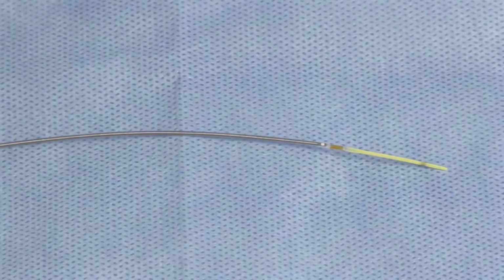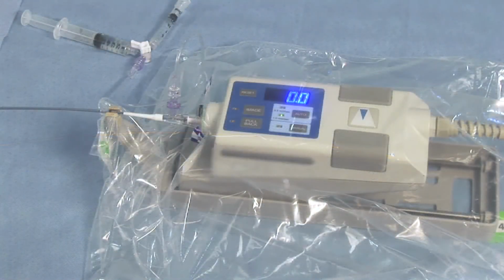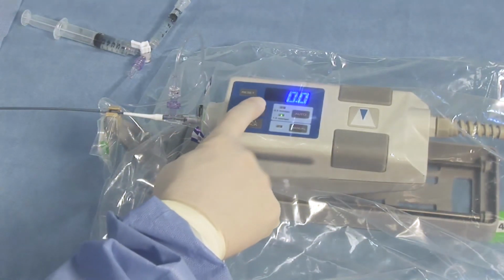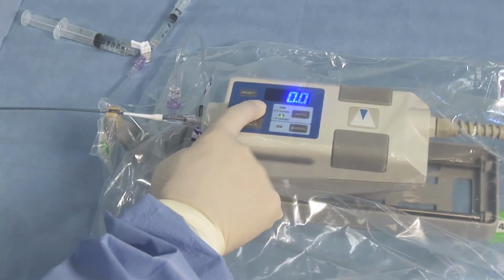Ensure the imaging core is at its full distal position. Examine the imaging core within the clear distal shaft to ensure no air is in the system. If air is present, reflush. To ensure proper function of the catheter, before advancing the catheter, check the image by pressing the Image button on the PIM and observing a pattern of partial bright concentric rings on the monitor.